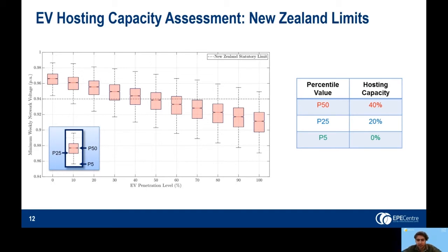The 50th percentile hosting capacity can be calculated by drawing a line which connects the P50 values on each box plot, as can be seen now. The first constraint occurs at the 50% penetration level, and therefore the 50th percentile hosting capacity is 40%. That is one penetration level below the point at which the first constraint is observed.